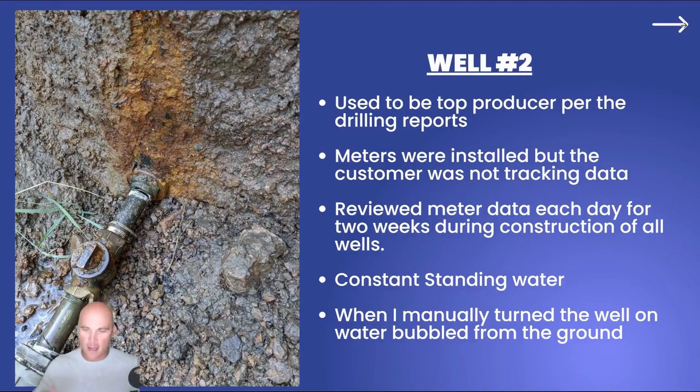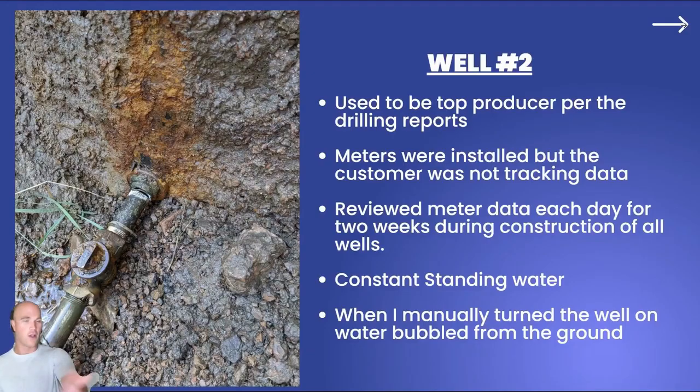So I got the operator. We came down and I said, can you turn this on just so I can watch the meter? And when he turned it on, I looked down to the ground and there's water bubbling up. So lo and behold, we dig it up, we find this issue, we fix it. But this taught me an important lesson.